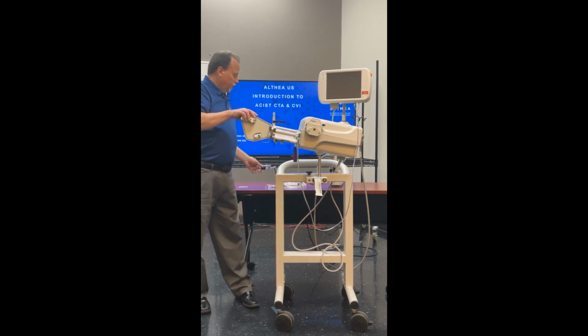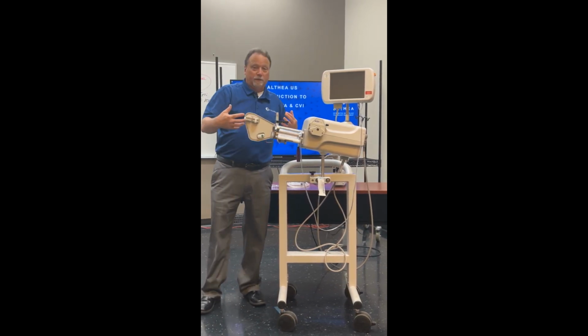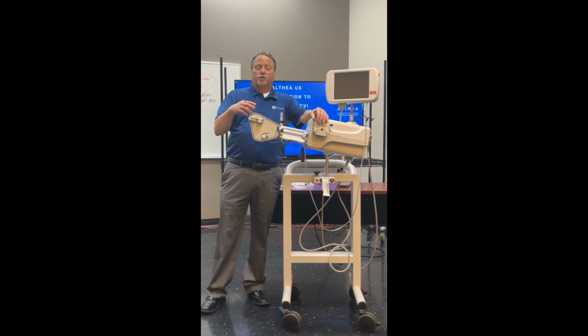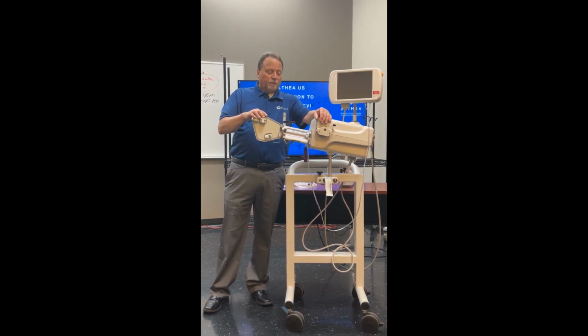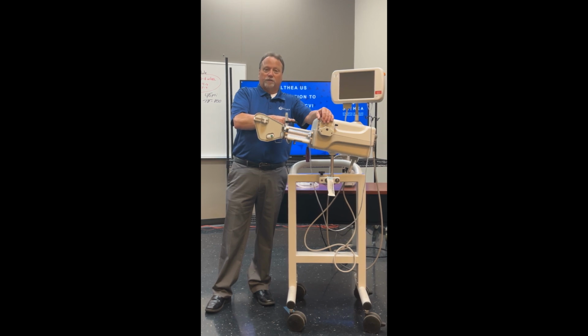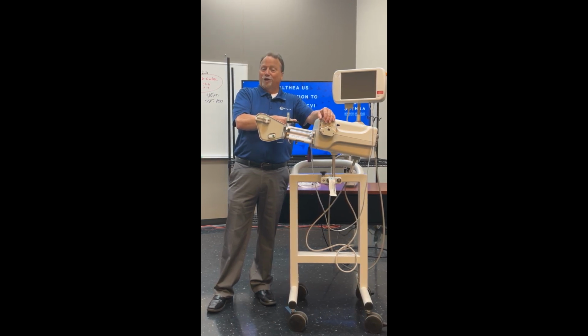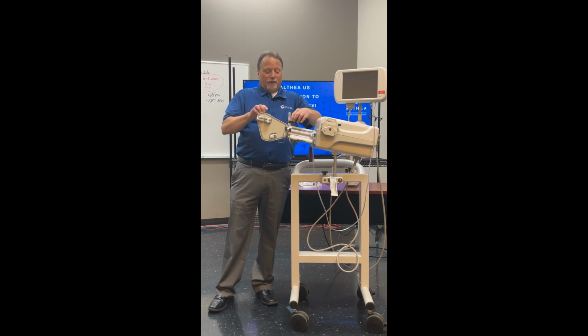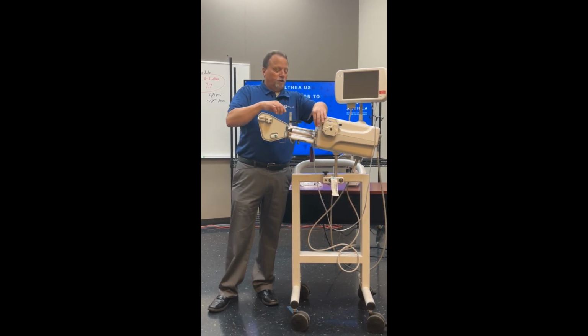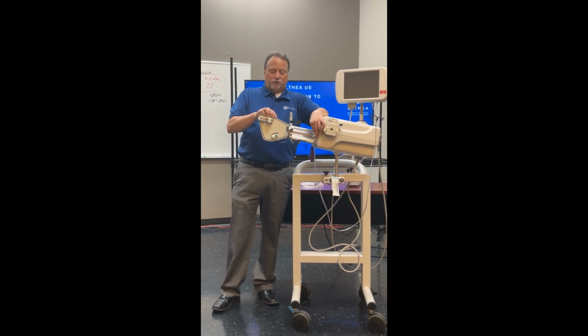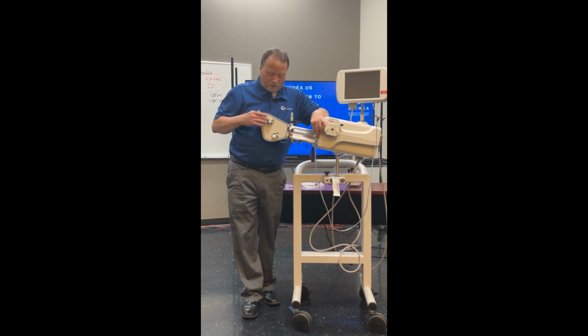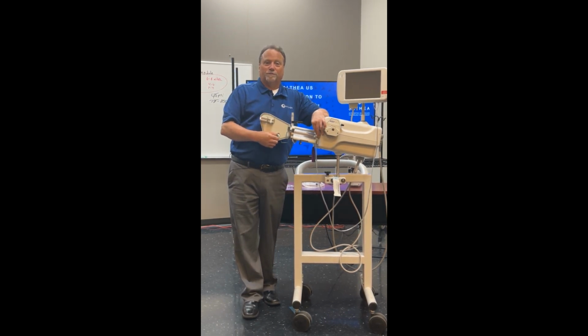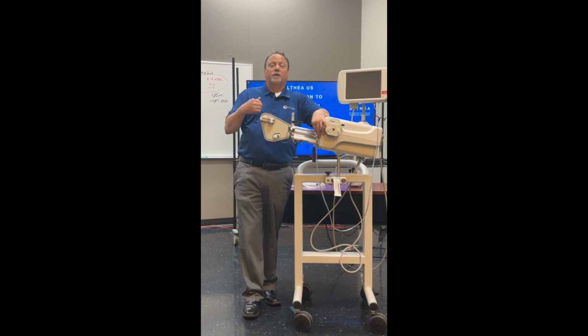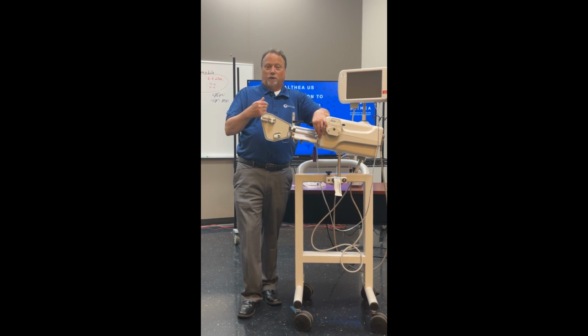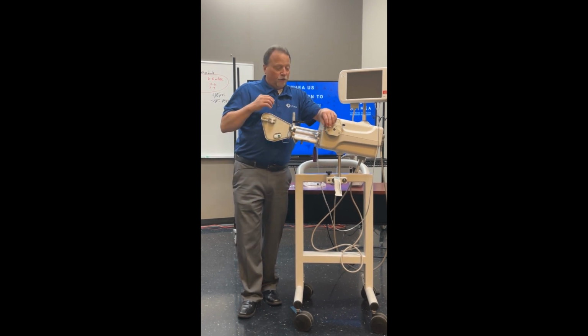Another unique feature on this, because it is all automatic, is that you have multiple sensors on here. One is a contrast sensor that identifies if there's contrast to be filled into the syringe. As I mentioned, the syringe sensor, you also have a chamber sensor, air column detect sensor, and a manifold sensor. With it being automatic, you have to have more sensors to ensure that things are working properly. And I'll get into those just a little bit later.